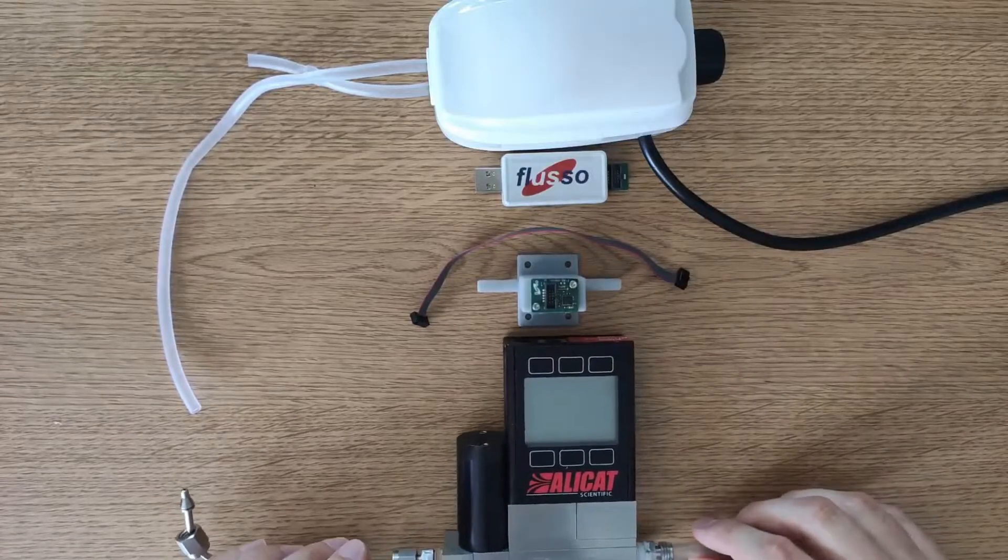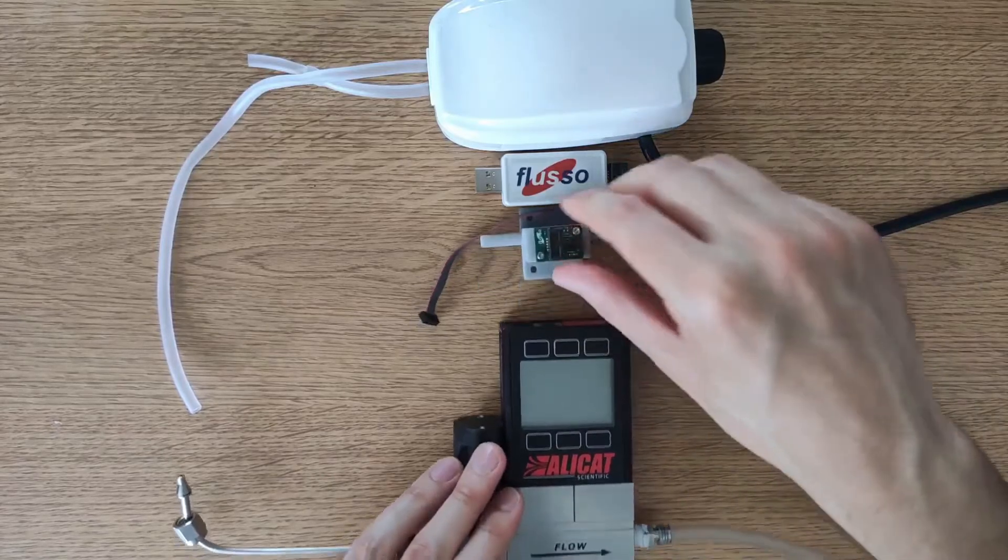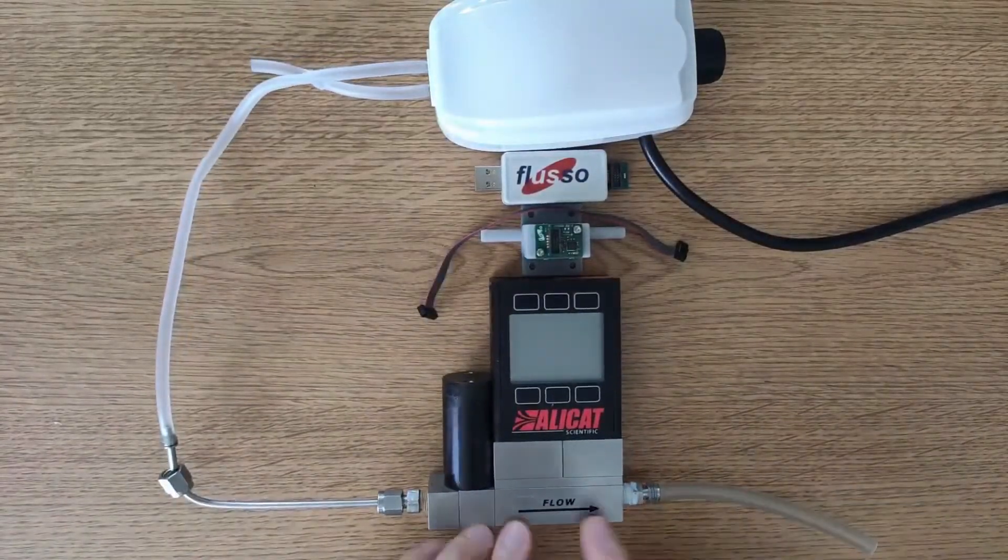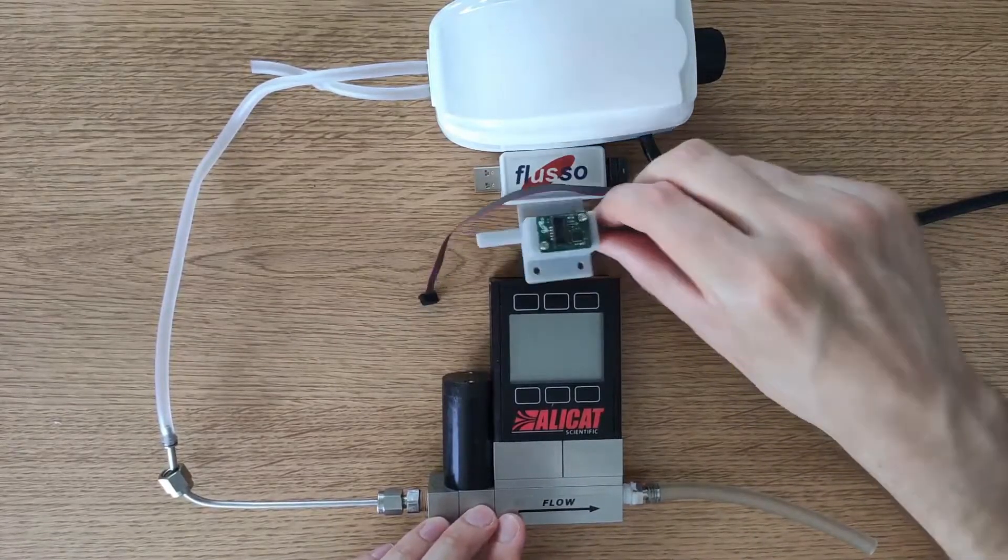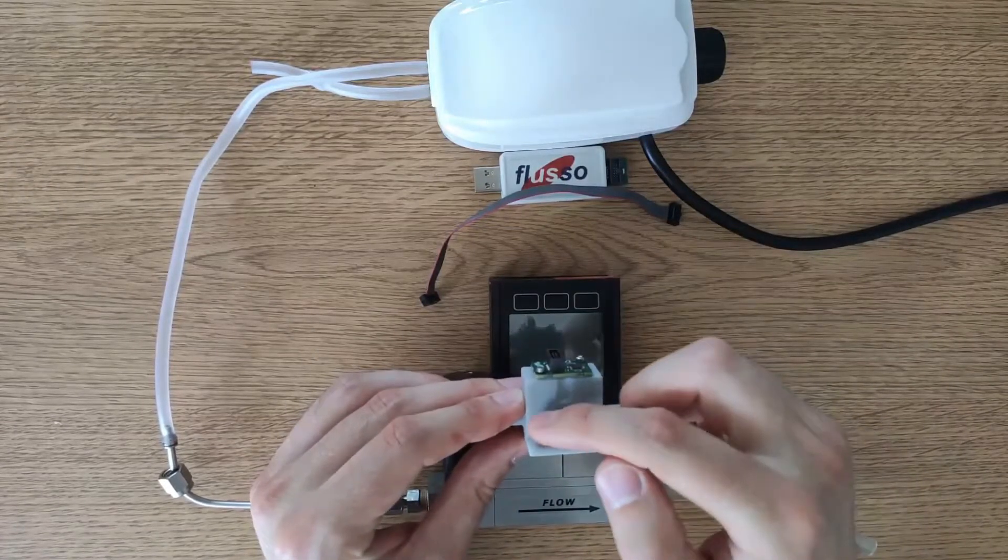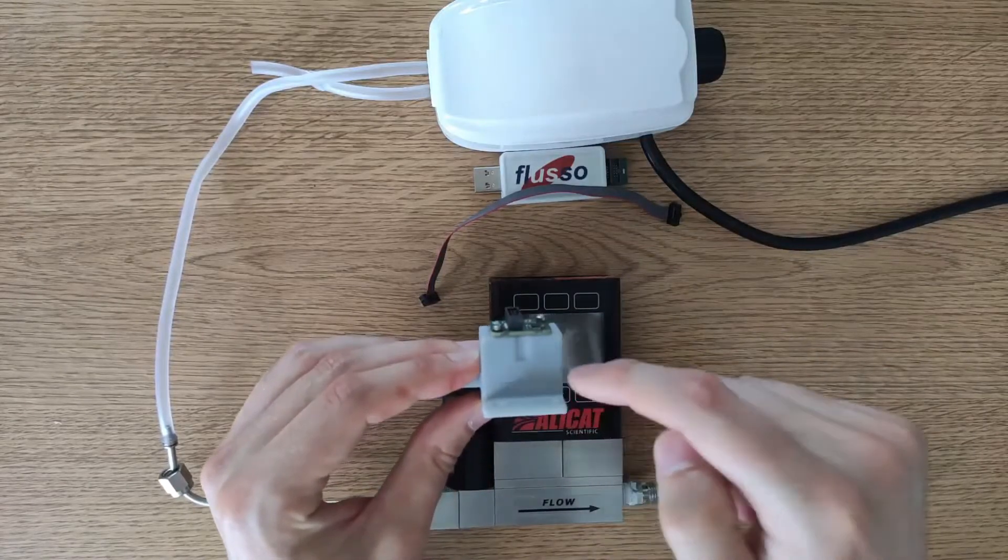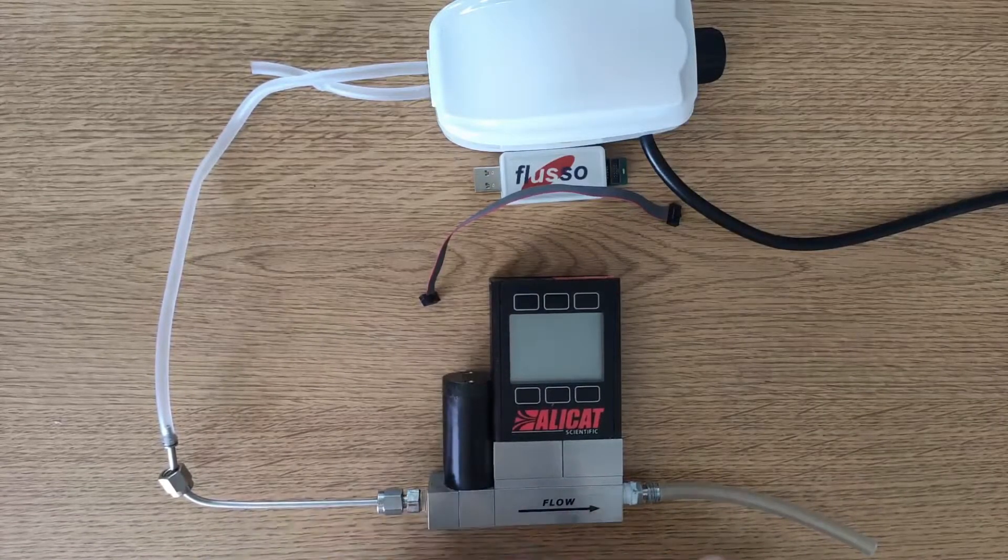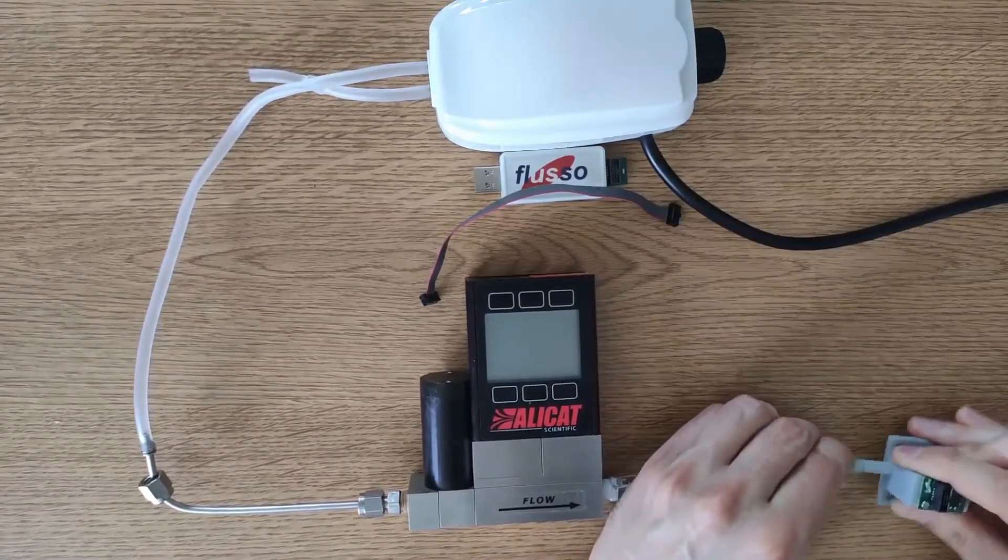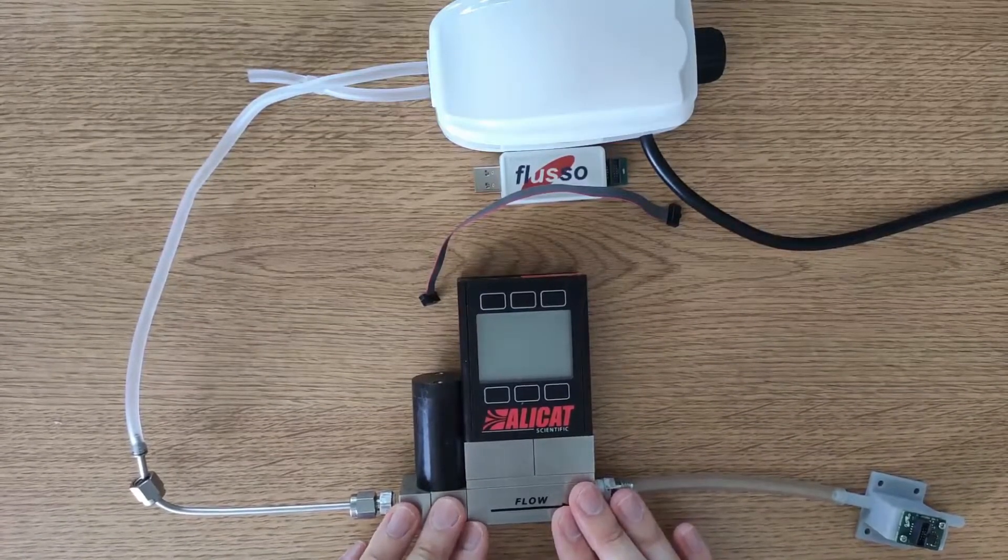In order to start evaluating the FLS110 we need to connect all these components together. The first thing we're going to want to do is connect the outlet of our fish tank pump to the inlet of our MFC. Flexible tubing makes this so easy. Once you've done that you're going to want to connect the outlet of the MFC to the inlet of your flow fixture. Your flow fixture will have an arrow on it marking the direction of flow. Mine goes from left to right and we want to make sure that if there is an arrow on your mass flow controller that's also going the same direction. Then we simply connect the flow sensor module to the outlet of the MFC like so. And that's all the fluidic connection that we need at this stage.